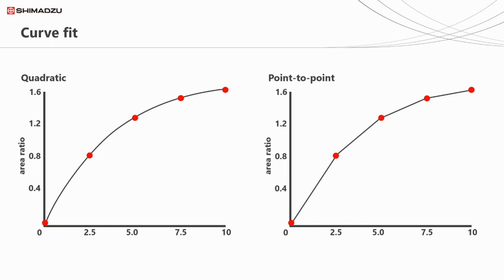In terms of curve fitting parameters, the first is the shape of our curve. In most methods, we use a linear curve — so it's not a curve at all. But we can also have an actual curve, such as a quadratic curve, which is common in specific applications or with detectors like the FPD when quantifying sulfur. Other curve fits are also possible, such as point-to-point, although these are less commonly used.